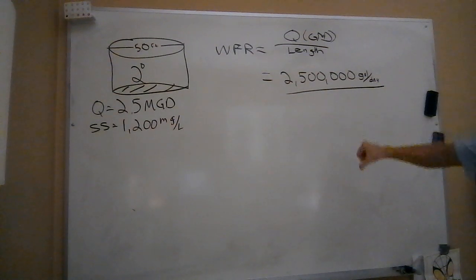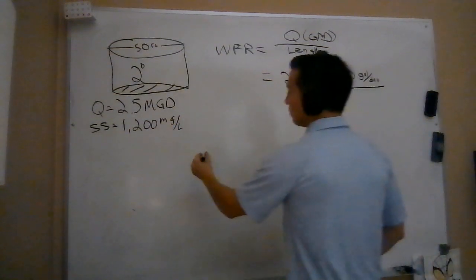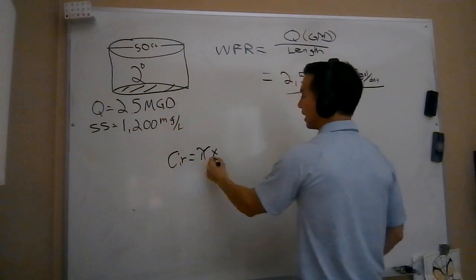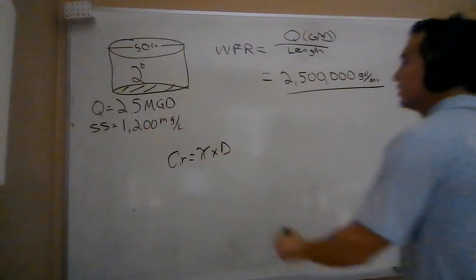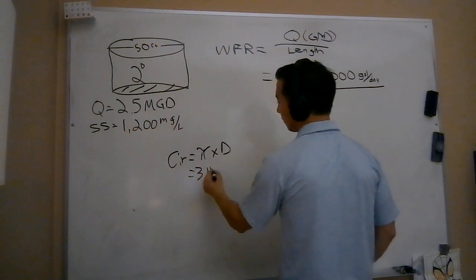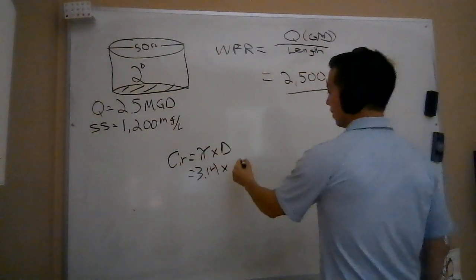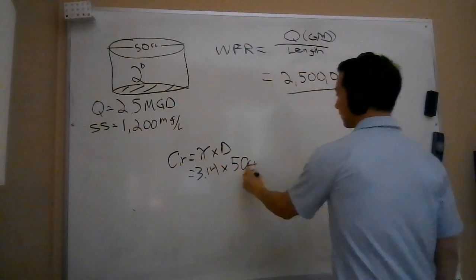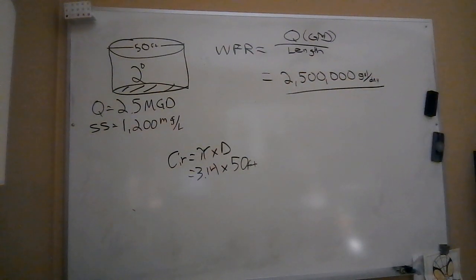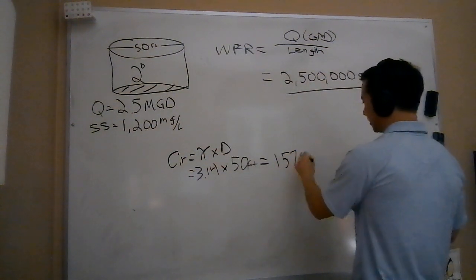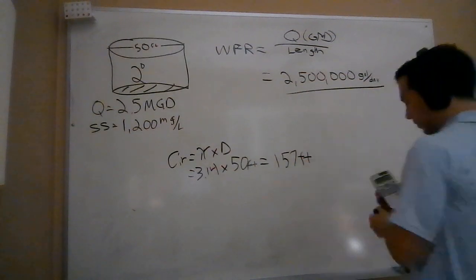Now I'm not directly given the length. If I plug in 50, that's going to be very wrong - that's the diameter. So I need to remember that the circumference of a circle is pi times diameter. A lot of times in wastewater math we just use 3.14 for simplicity. In this case, I have a diameter of 50 feet. So if I do 3.14 times 50, I get to 157 feet of weir. Notice those units - it's feet, not square feet. We're dividing by a length.